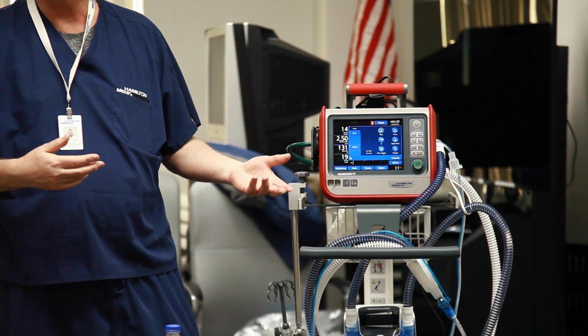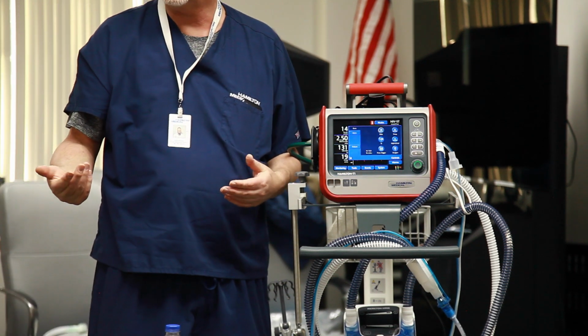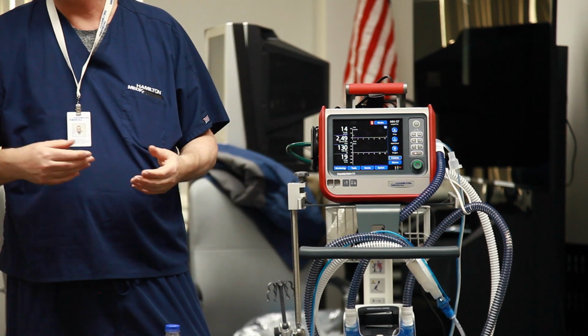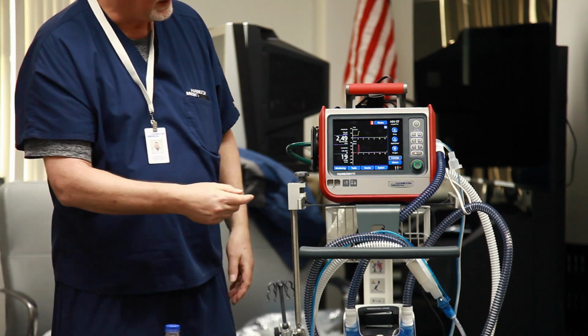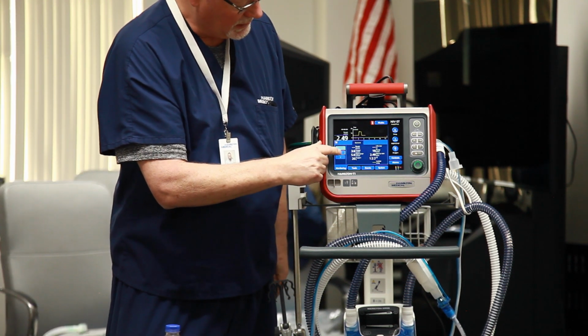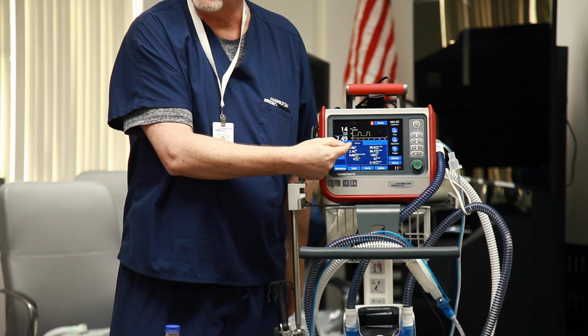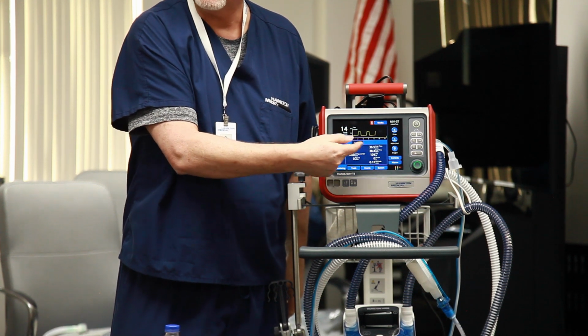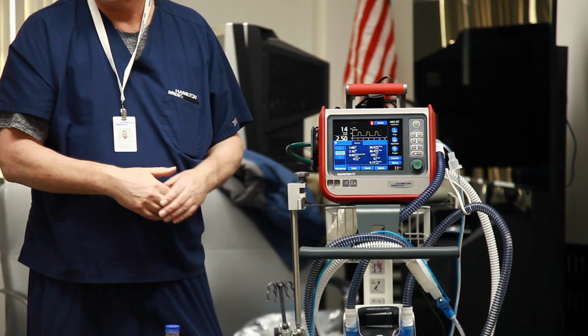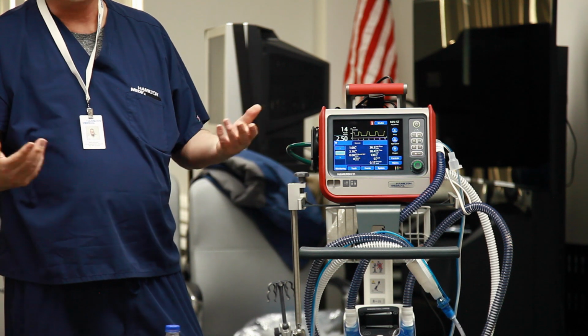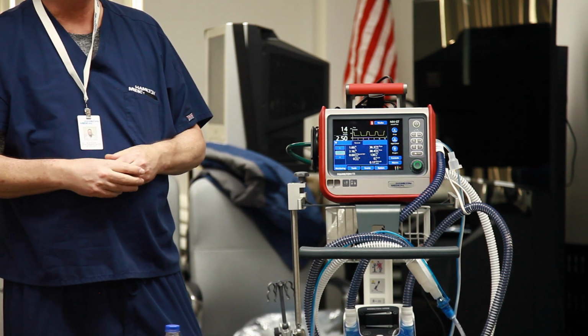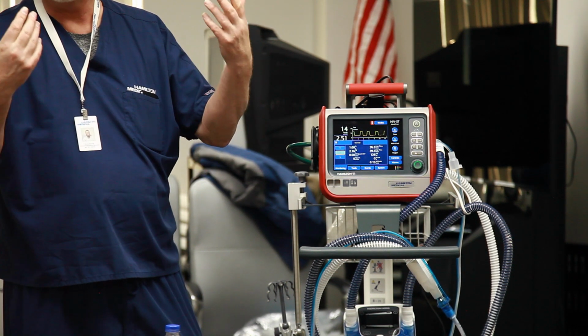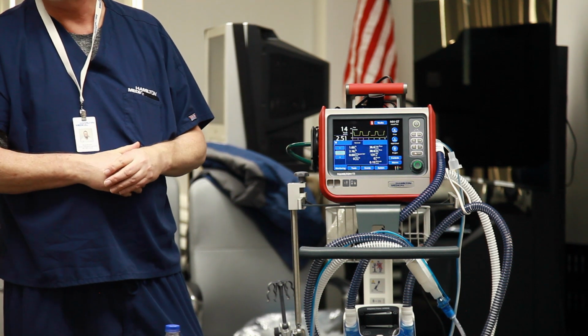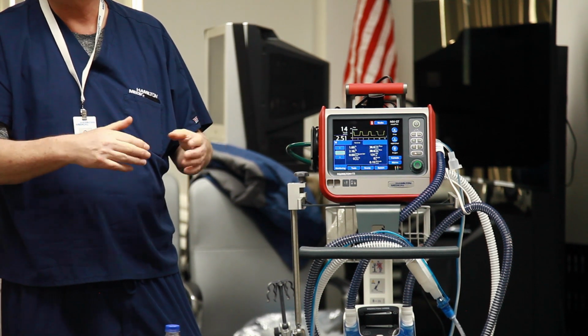Depending on the height, it's going to be probably between 0.8 and 1 second. What I will do a lot of times is go to my monitoring page, see what my I time is spontaneously, and then set it at that. That's where it's going to default with the height generally, and that's a pretty decent default. But if they're breathing a little faster, you might want to shorten that up.